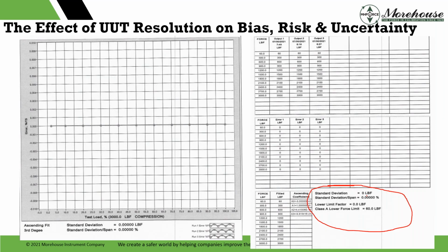And if we set resolution coarse, that can fool almost everything as far as your pass fail and well, if you do it properly, it won't. But if you don't do it properly, then you can get things like this, where standard deviation is 0. This is an example of a cert that should never happen. And it's an actual example from an accredited cal provider.